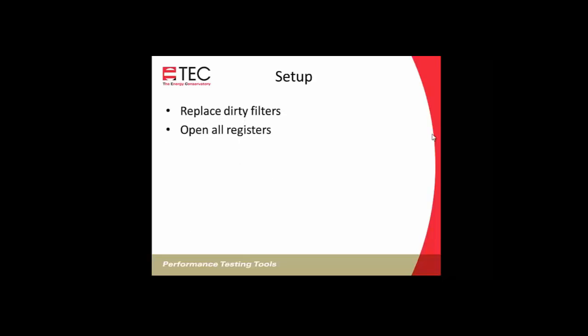We'll want to make sure all the registers are open, so we'll get the maximum flow through the system. We'll want to open a window. If when we turn on the air handler, it changes the pressure in the room, that's a problem, because we're reading the operating system pressure with respect to the room we're in, and if the pressure in the room changes, then we're getting the wrong number. So we want to open a window to the outside. If our air handler is in a crawl space or an attic or a garage, we'll want to open that space to the outdoors. So turning on the air handler won't affect that pressure.